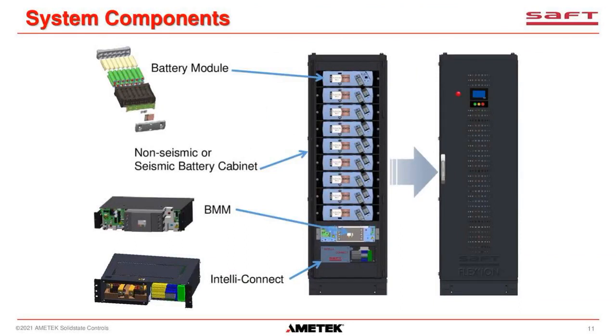So this is what makes up the SAFT lithium-ion battery. We have a cabinet, shown here. You can have multiple cabinets in parallel to make a larger battery with a larger capacity. But this one cabinet has 9 battery modules. You can also have a version with 5 battery modules for a 120 volt DC bus. What's shown is for a 240 volt DC bus.